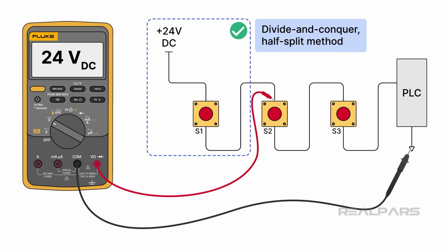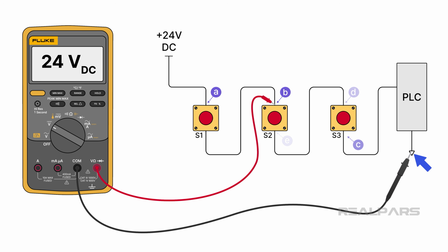Of course, this sounds great on paper, but it boils down to not having to crawl on the floor or perform Houdini-style maneuvers to place the red DMM probe where you want it. Okay, let's do it. We clamp the DMM black probe to the 0 volts DC common point on the PLC. We place the red probe on point B.